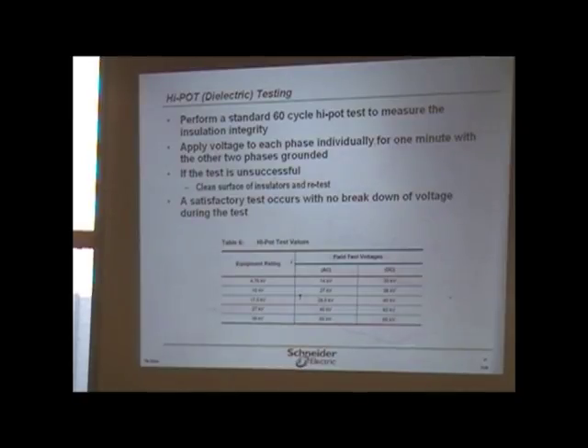Have you ever used a hi-pot before? No. It's the same thing as a megger. You notice when a megger breaks or when it hits the ground, it does the same thing with a hi-pot. Hi-pot is no different really, other than it's got higher voltages and everything else, whether it's AC or DC. But what I was going to show you is to say, okay, 5 kV, and I said 2.5 times.